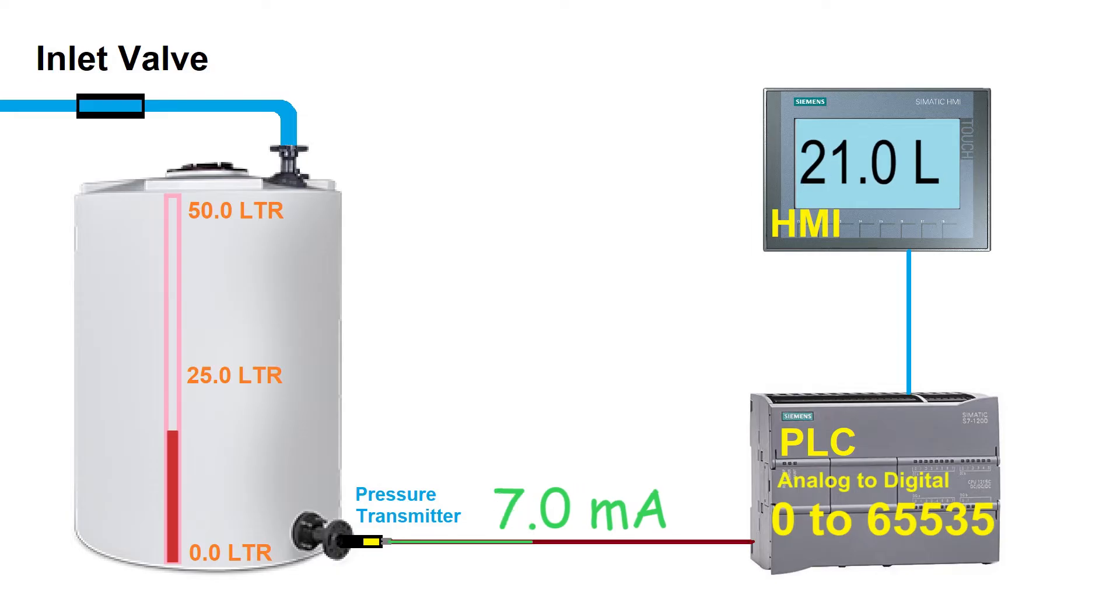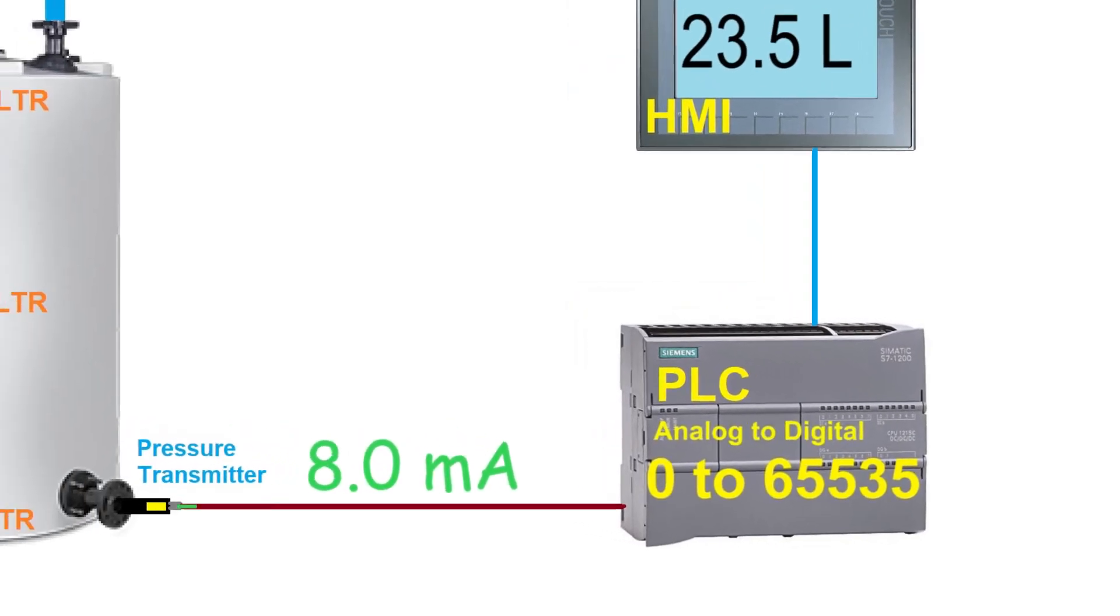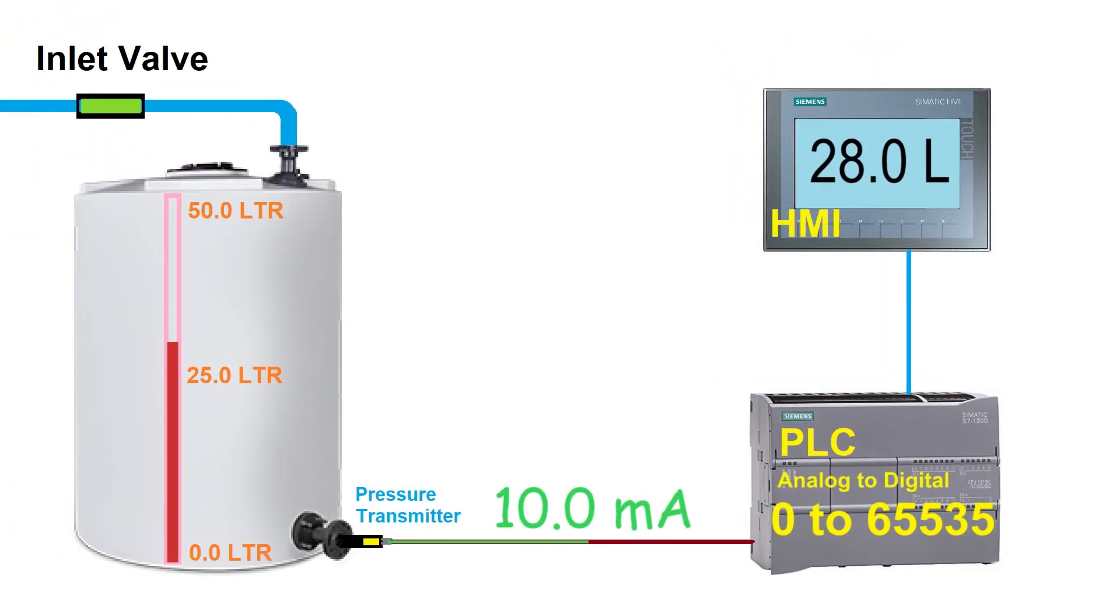Now this analog signal is converted to digital values from 0 to 65535 by the PLC. Usually it is referred as a raw sensor value and then scaled to 0 to 50 liters by PLC using some formula and this will go to the HMI display.